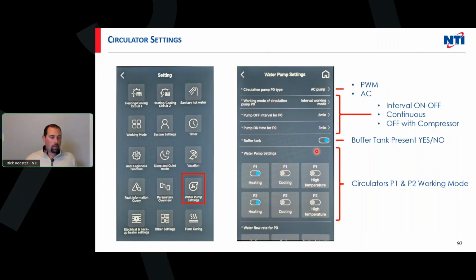Another popular setting that we may need to get into is the water pump settings. If we're using a hydro box, a lot of this is programmed as far as the P0 pump. But if we're using a control box where we don't have a circulator, one's going to be supplied by you guys and a contractor, then we have to go in and tell it what we're working with. We have to tell it that we're using an AC pump and not a PWM like our hydro box. We then have the ability to change our working mode, whether it be interval, on, off, continuous, or off with the compressor. So we have the ability to control that.